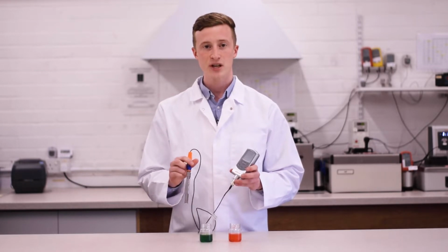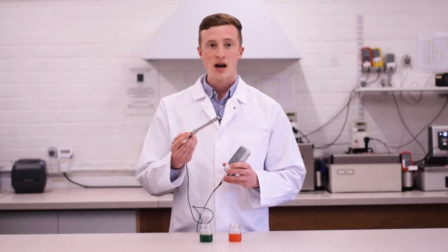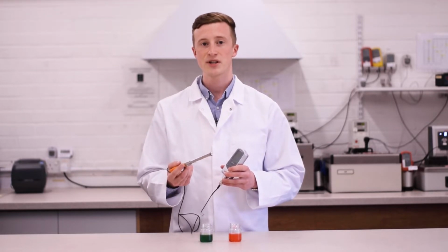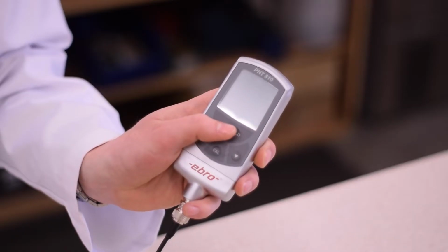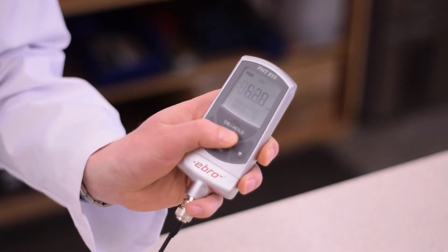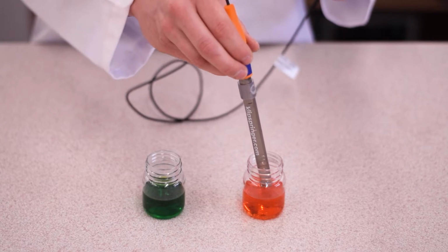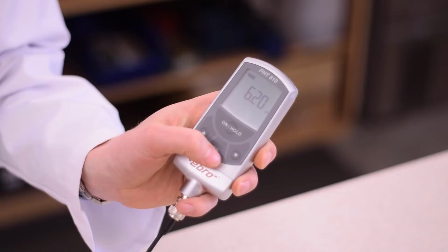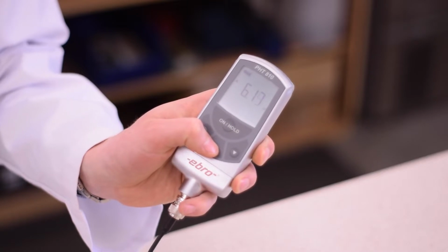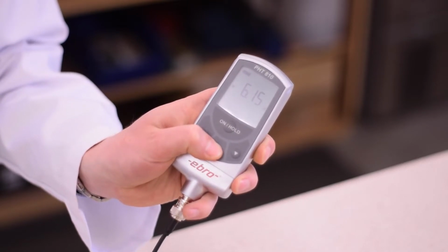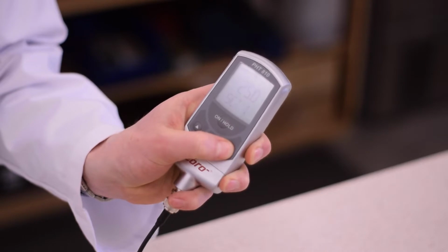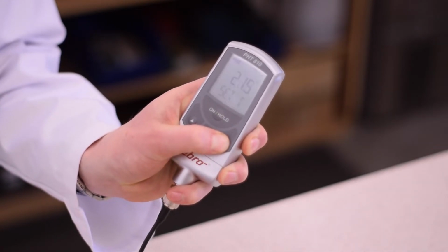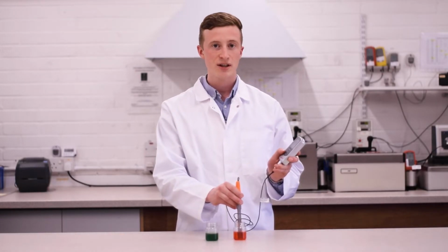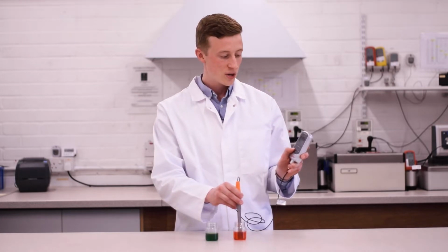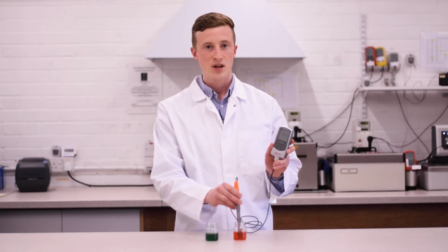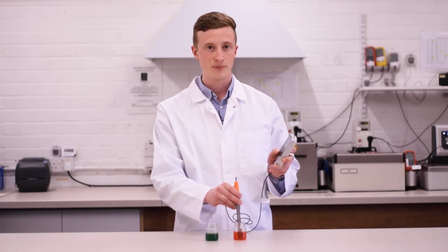Before calibrating, ensure the electrode is clean, using cleaning solution and a non-abrasive tissue if necessary. Switch the unit on and place the electrode into your first pH buffer solution. Press the cal button, then select the product temperature using the up and down arrows. Next, change the number of calibration points to 2 using the up and down arrows again. Confirm this by pressing cal.